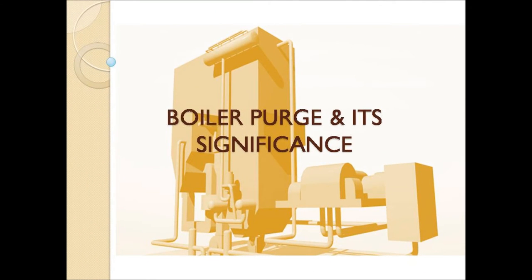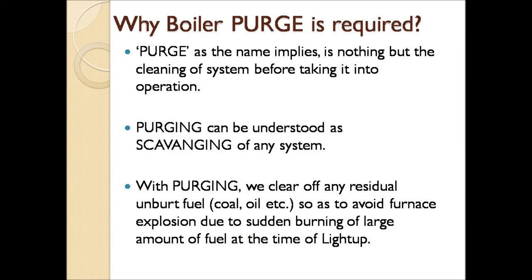Hello and greetings to all. Today we will discuss a very basic topic of boilers: boiler purge and its significance. First we will see why boiler purge is required. Purge, as the name implies, is nothing but the cleaning of a system before taking it into operation. Purging can be understood as scavenging of any system. We clear any residual unburned fuel so as to avoid furnace explosion due to sudden burning of a large amount of fuel at the time of light up.